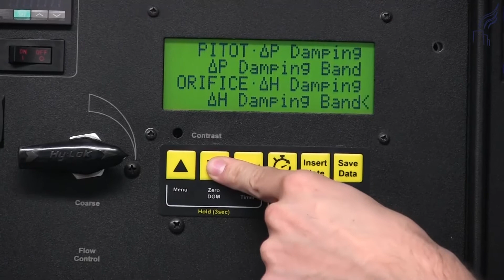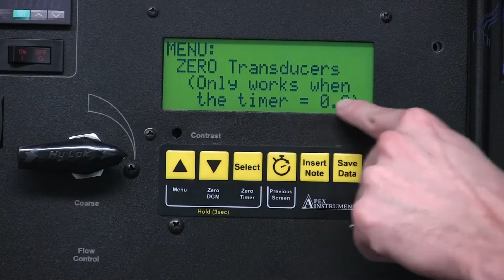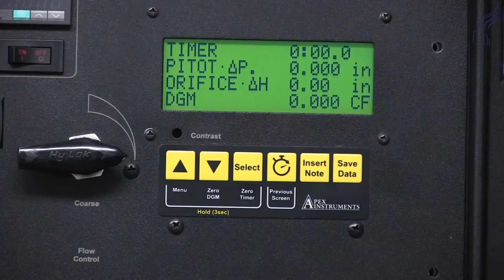Press select. You will get a zero transducers message, and in brackets it'll say only works when the timer equals 0. Press select, and you can press the timer button to exit out to the main menu screen, and your deltaP and deltaH transducers will then be zeroed.